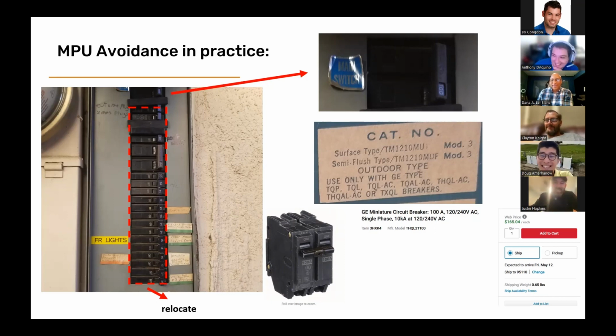Well, the output of the IQ battery is significantly smaller. You've got 3.8 kilowatts, about 14 to 15 amps you can run, so it's not going to run very much. The Franklin, on the other hand, runs at a continuous 21 amps and can throttle all the way up to 42 amps for 10 seconds. So there's a big difference. We're not so much limited by the number of breakers as by how much work your electrician wants to do.